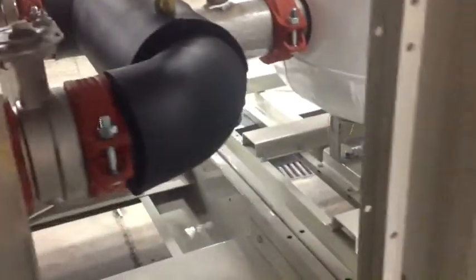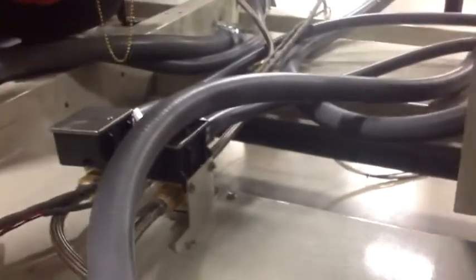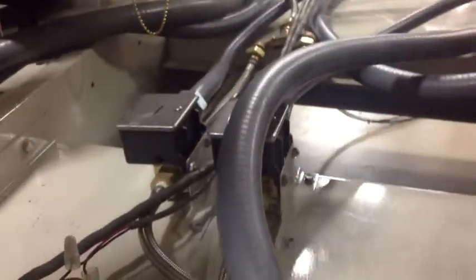And we follow down the hard pipe into the suction side at the common piping that comes from the bottom of the storage tank. The braided hose there in that sensor location is one input for our DPs, which provide proof of flow. There are the 2 DP switches. We have 2 for redundancy. We'll pan back here and see the T so that we have 1 sensor location, but it T's into 2 DPs. We'll pan up so you can see the discharge side of that differential pressure tap right there. And then this is back on the front side of the chiller showing those DPs and where they enter the pump control panel.